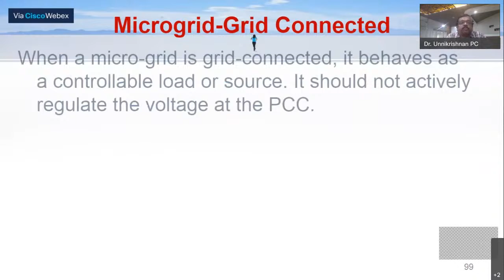Whenever there is an abnormal condition in the grid, or it may be in the microgrid, the static transfer switch will be disconnected and the microgrid will go into an islanding mode. When the microgrid is connected to the grid, it has nothing to do because the grid will take care of everything. So the microgrid is just a load. Whereas when the microgrid is in islanding mode, it has to take care of all the activities within the microgrid. It has to monitor the generation and the load, and at any point of time there should be a power balance, that the generation and the load should be equal. So we call it load dispatching.